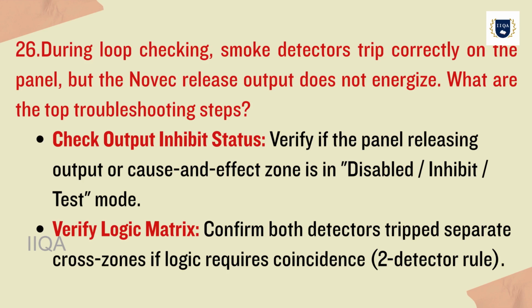26. During loop checking, smoke detectors trip correctly on the panel, but the Novec release output does not energize. What are the top troubleshooting steps? Check output inhibit status. Verify if the panel releasing output or cause and effect zone is in disabled, inhibit, or test mode. Verify logic matrix. Confirm both detectors tripped in separate cross zones if logic requires coincidence 2-detector rule.